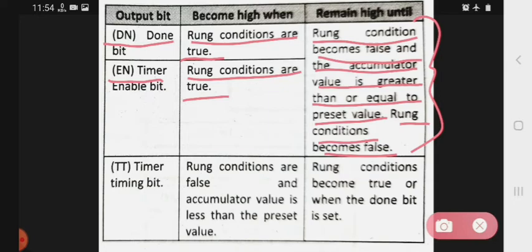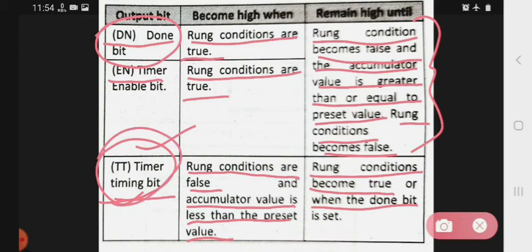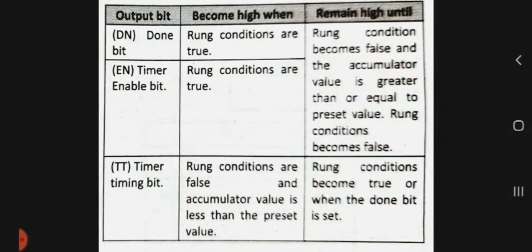Next, let's look at the TT bit, that is the timer timing bit. The TT bit is high when the rung condition is false and the accumulator value is less than the preset value. It remains high until the rung condition becomes true or the done bit is set. So the TT bit stays high while the timer is actively counting down after the rung goes false.